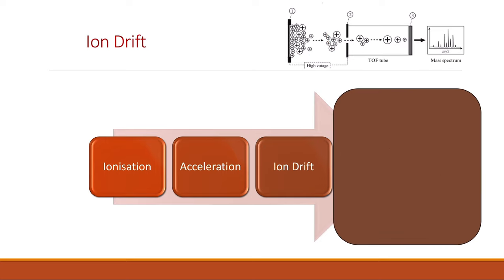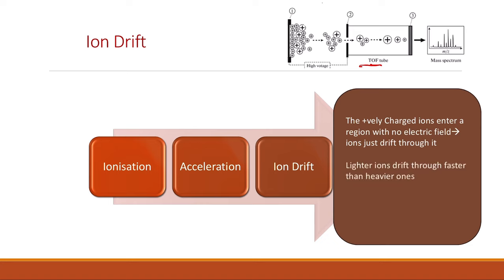The second stage is acceleration. The positively charged ions are accelerated by an electric field, and all the charged particles will have the same kinetic energy, so the lighter ones will move faster than the heavier ones. The third stage is ion drift. The positively charged ions enter a region with no electric field — the time-of-flight tube — and just drift through it. Lighter ions drift through faster than heavier ones, reaching the detector sooner, and they move at different speeds.